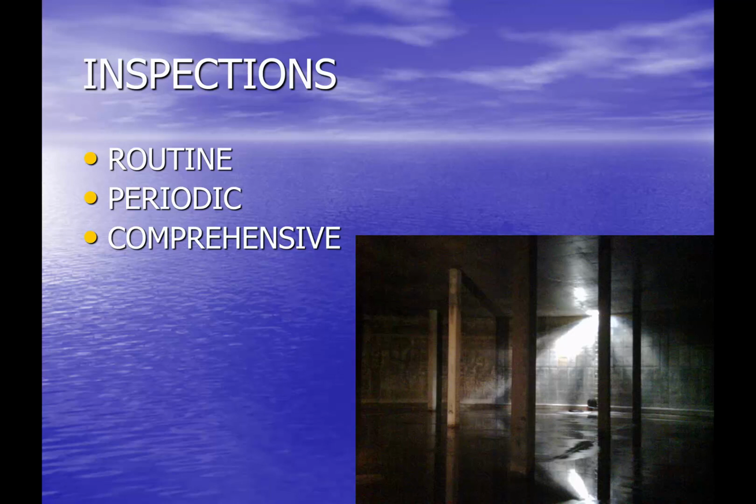So we're looking at the coatings, we're assessing the reservoir, any kind of structural issues, we're looking for corrosion, and we're looking certainly for any evidence that anything might be wrong with the tank itself. If we talk about some types, especially of interior inspections, how can we see the interior of a reservoir?